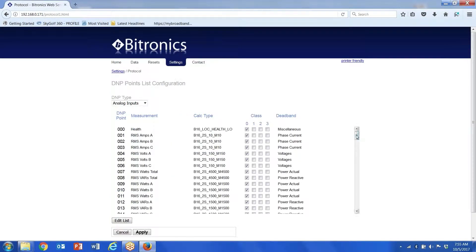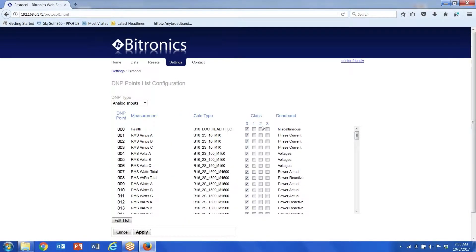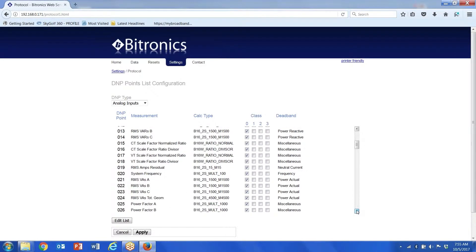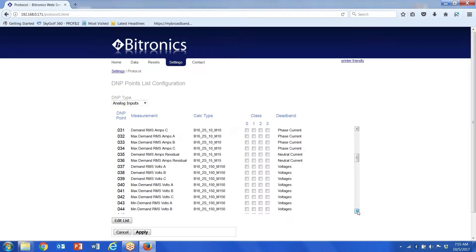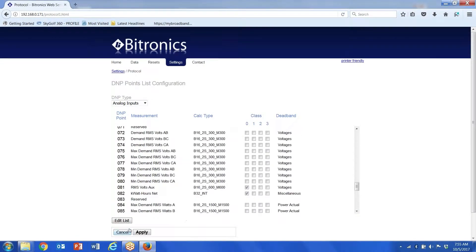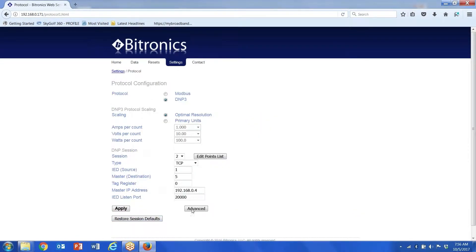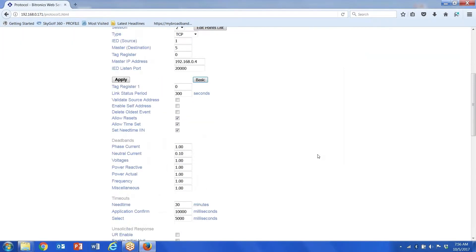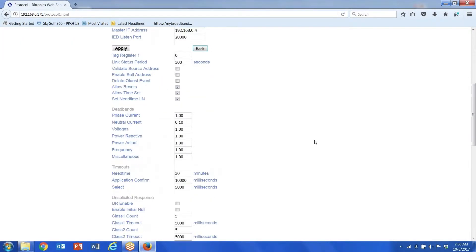Here's the points list that's available. Notice on my particular meter I have all of these values selected for a class zero response. This is what the values are going to report to the RTU when the RTU does an integrity poll.